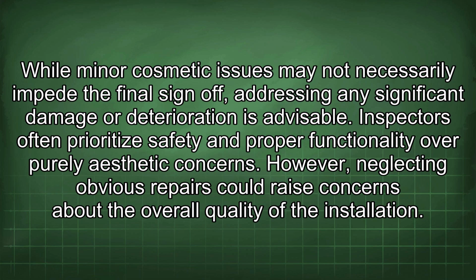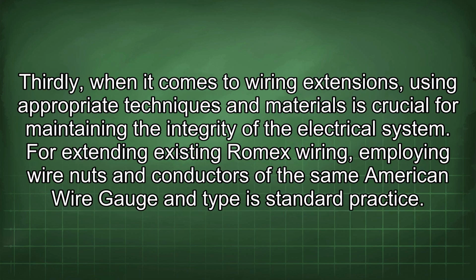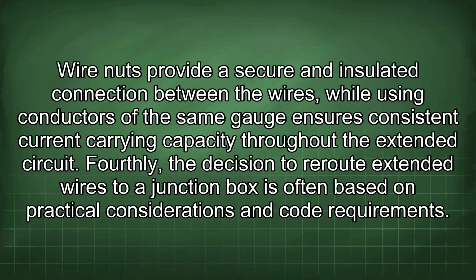However, neglecting obvious repairs could raise concerns about the overall quality of the installation. Thirdly, when it comes to wiring extensions, using appropriate techniques and materials is crucial for maintaining the integrity of the electrical system. For extending existing Romex wiring, employing wire nuts and conductors of the same American wire gauge and type is standard practice. Wire nuts provide a secure and insulated connection between the wires, while using conductors of the same gauge ensures consistent current carrying capacity throughout the extended circuit.